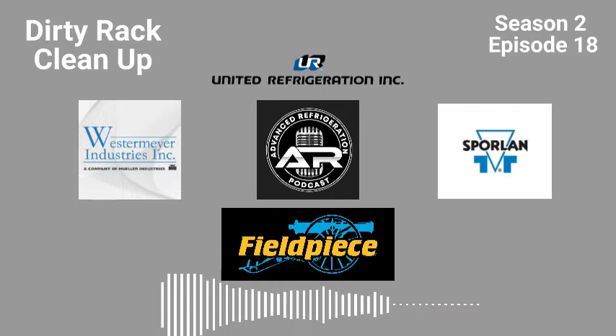Yeah, I remember you and me asked that, and Sporlan replied that their shells are only good to about 200 degrees, but the liquid cores were good too. Yeah, what were they rated to? So technically you'd probably get away with doing it. I have done it on a cool gas rack. I have added a shell dryer to a cool gas rack to clean it up that we had. That was absolutely a filthy abortion.